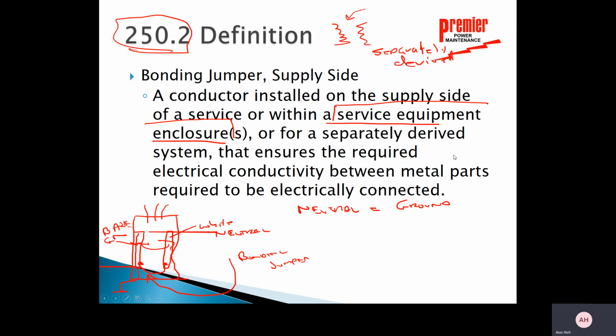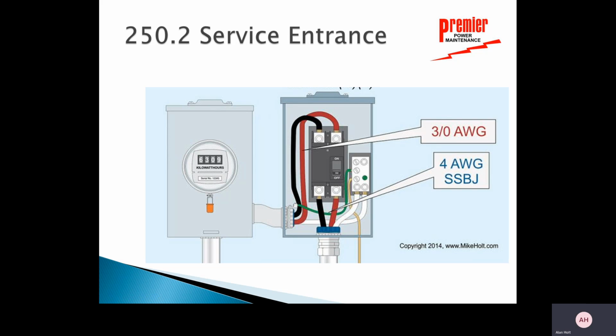So going forward, I look at that service entrance situation. So here's my kWh meter that we all have on our house, or the customer has. There are my two hot wires, 240 volts coming in. There's my neutral coming in. And going from this main disconnect here, main circuit breaker, I see that they're all leaving, going to the rest of the house or all my other loads. But I'll make a very quick notice that look right here.